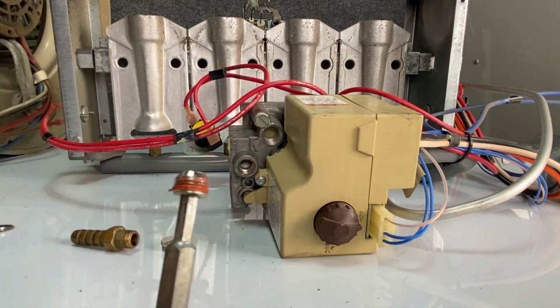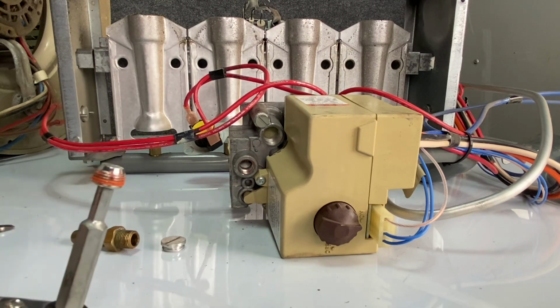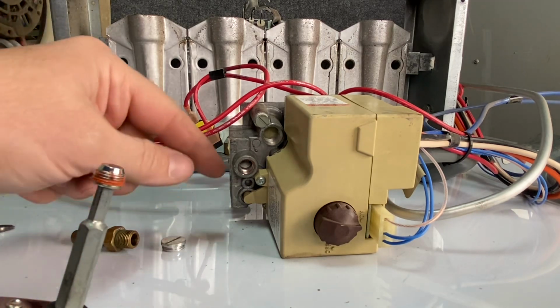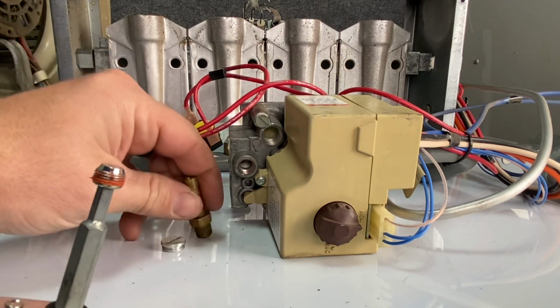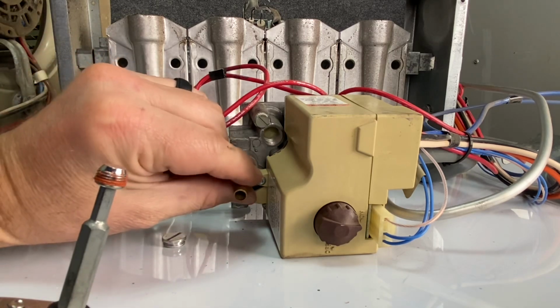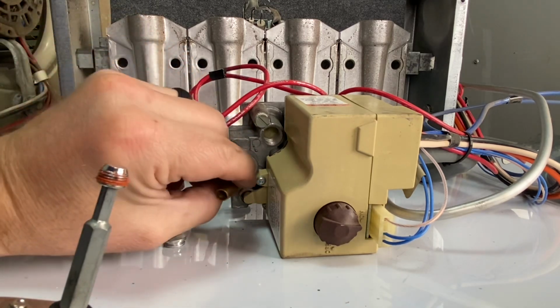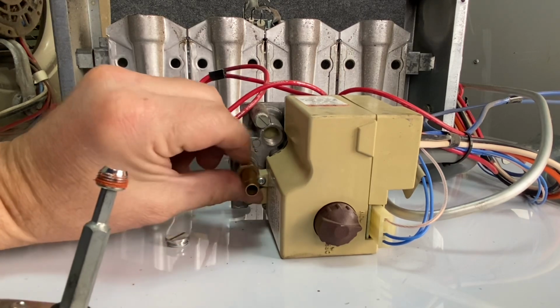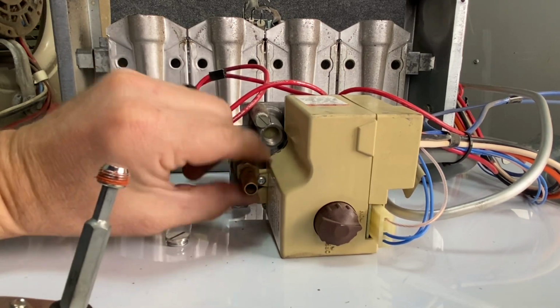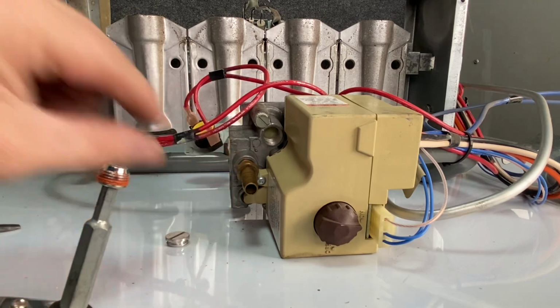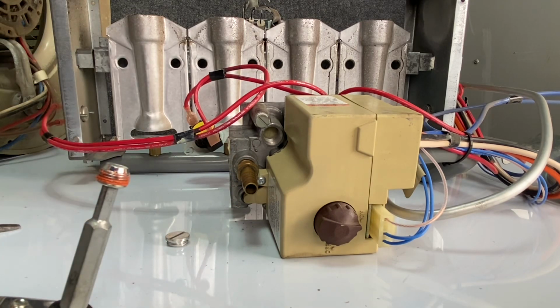This is the plug that comes out, and what we have with this would be open. So if the gas was on while I did this, gas would be pouring out, so you'd have to shut the gas off. You would put in this little adapter right here. Once you have your adapter, you could put your hose on this to your manometer, turn the gas back on, and you could check your gas pressure. Then you start the system up, and you could see what your incoming gas pressure was.